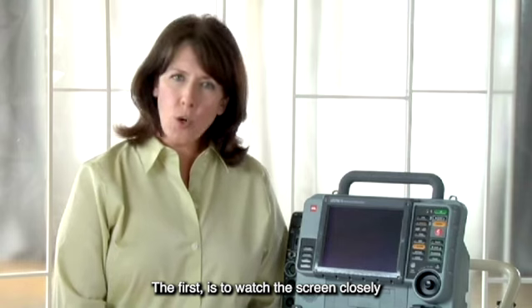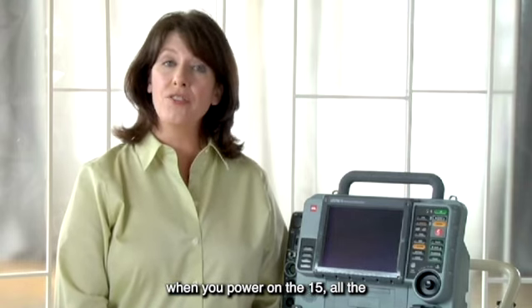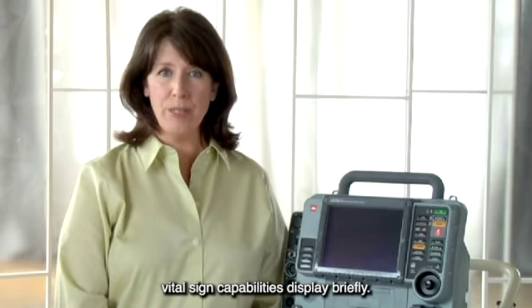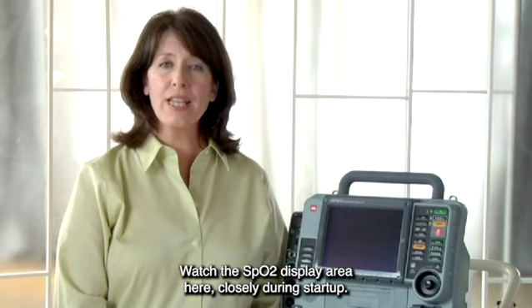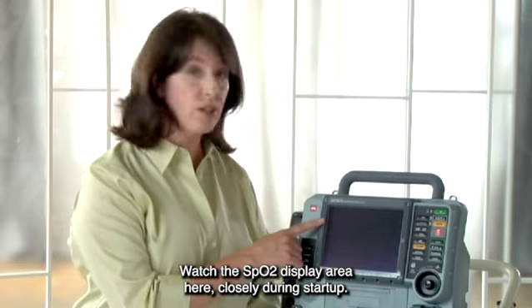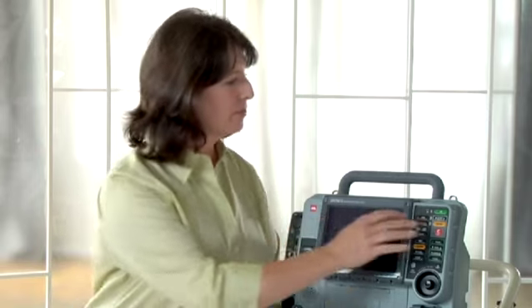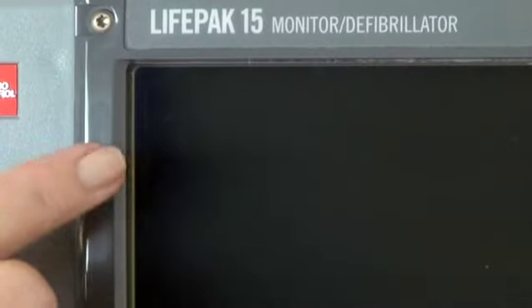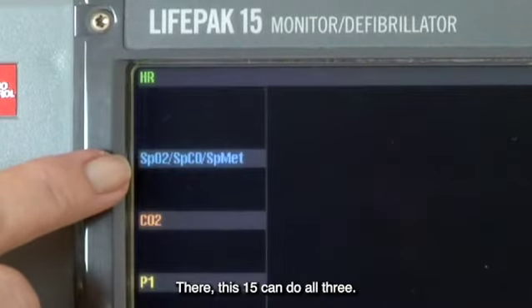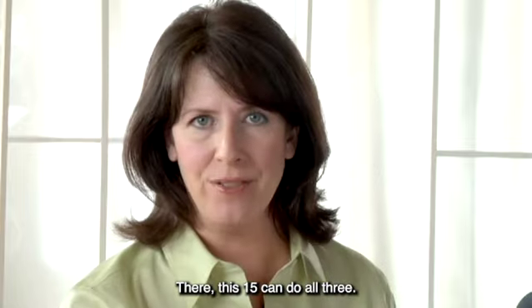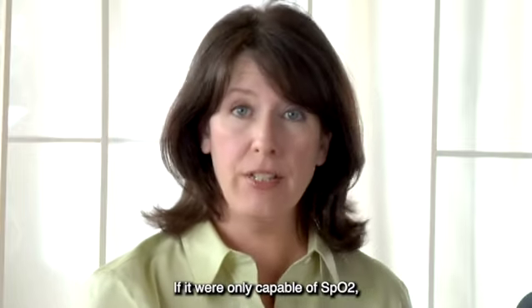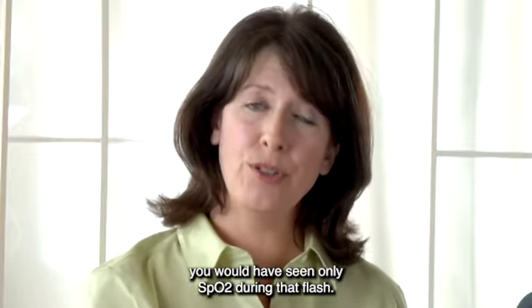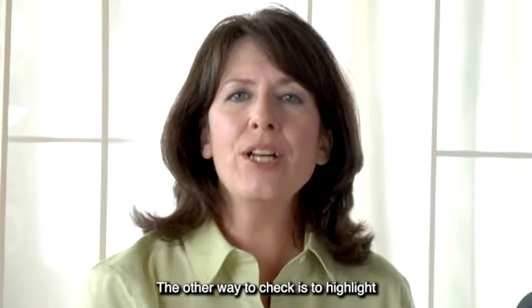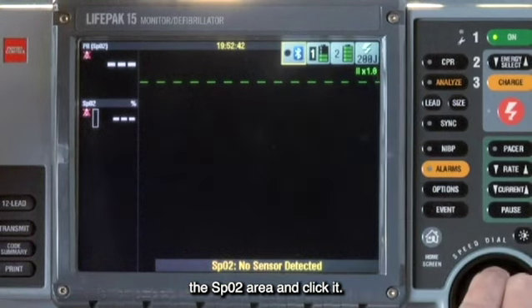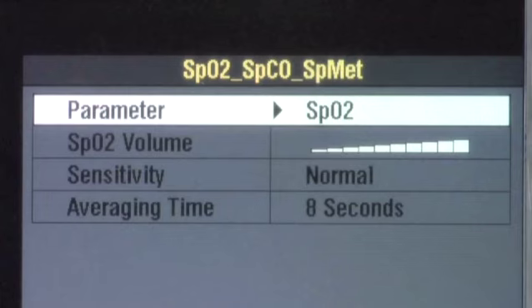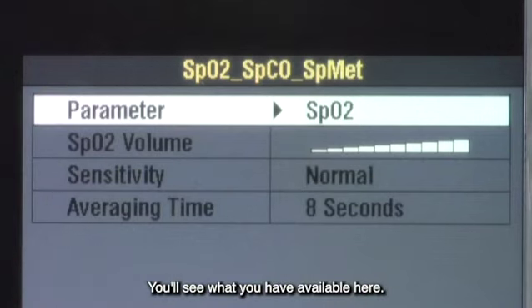The first is to watch the screen closely when you power on the 15. All the vital sign capabilities display briefly. Watch the SpO2 display area here closely during startup. There. This 15 can do all three. If it were only capable of SpO2, you would have seen only SpO2 during that flash. The other way to check is to highlight the SpO2 area and click it. You'll see what you have available here.